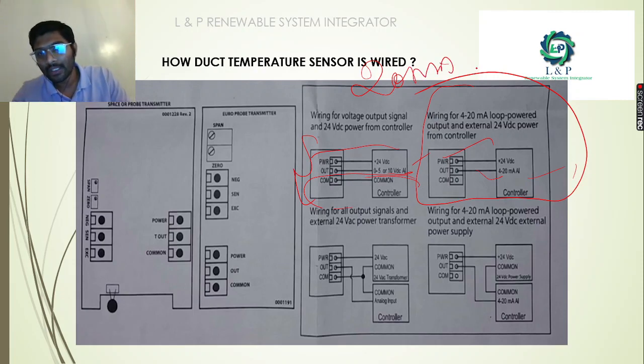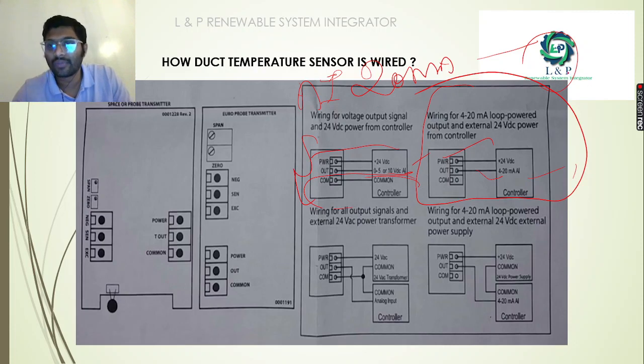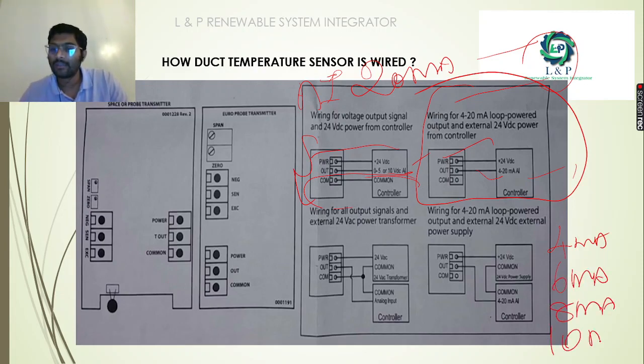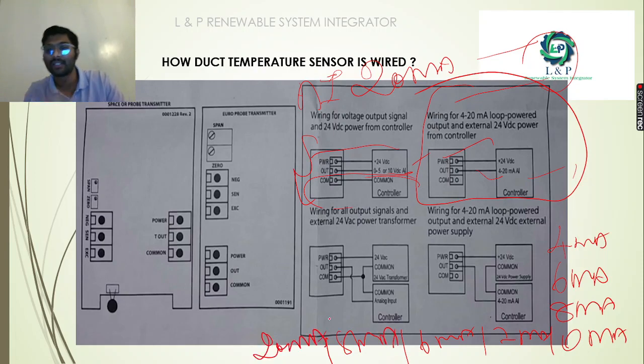From your analog input controller, because of the temperature changes, you won't get the exact 20 milliamps feedback. You will get either 4 milliamps, where there is no change. Now if it is 0 volt, if it is not operating properly, or at minimum temperature, you will get 4 milliamps. Otherwise you will get 6 milliamps, 8 milliamps, or 10 milliamps, or sometimes 12 milliamps, 16 milliamps, or sometimes 18 milliamps, even 20 milliamps output, based on the sensor that you choose.